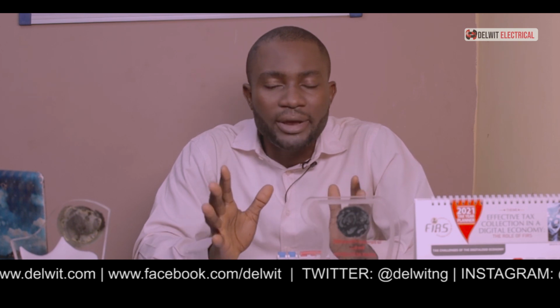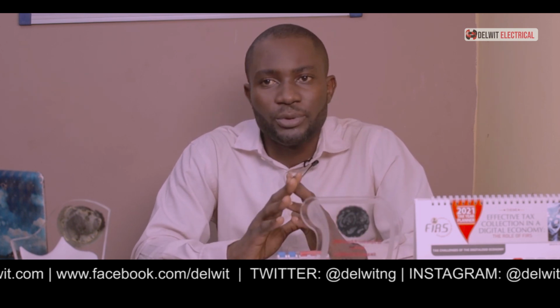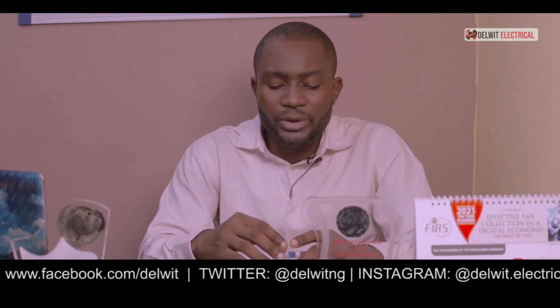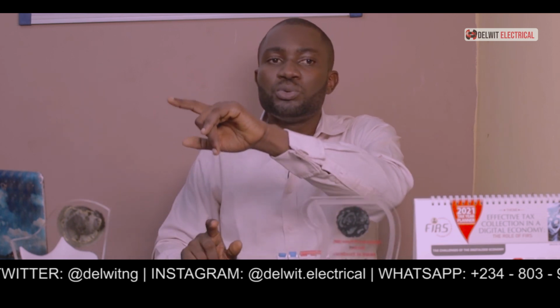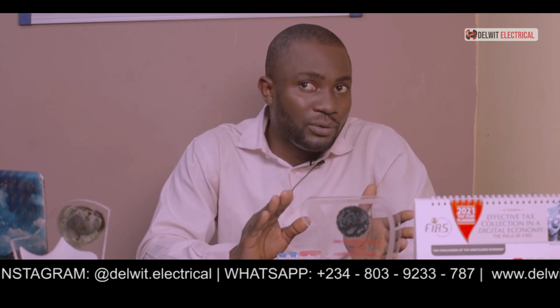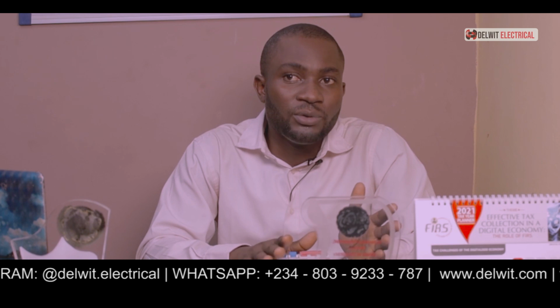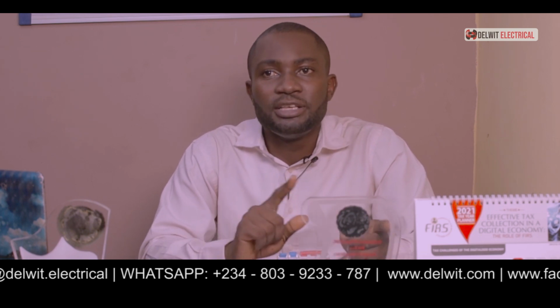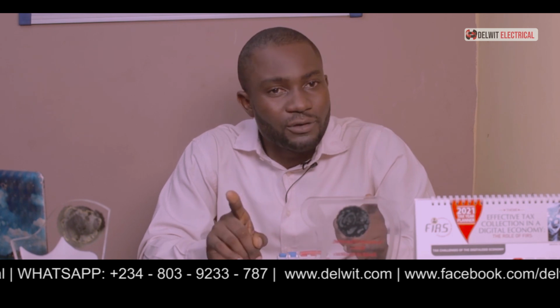That is why a descriptive labeling of your circuit breaker is very important. When a particular circuit breaker trips off, you go to your distribution board and check the particular circuit breaker that trips. When you look at it, you should be able to trace where that supply is coming from. Then you go and start tracing to know if it's not an overload. If you notice that there's not an overload, that means the live and neutral is actually touching somewhere. So you have to go and remove it before that fault can be cleared.